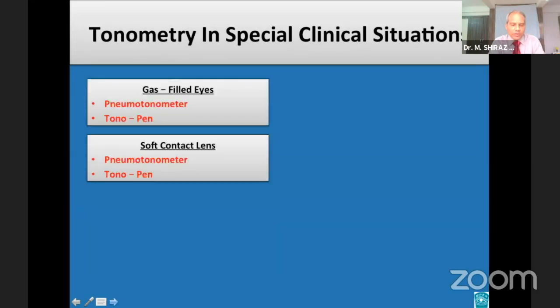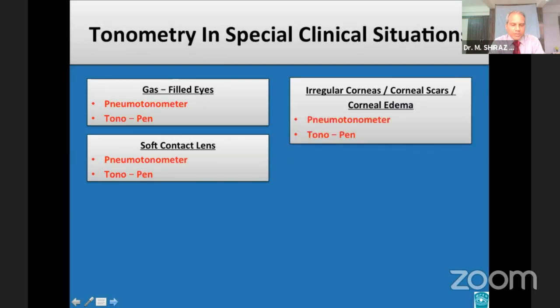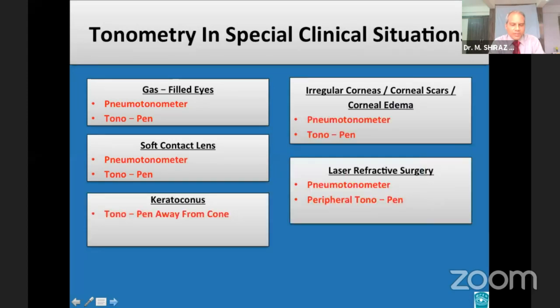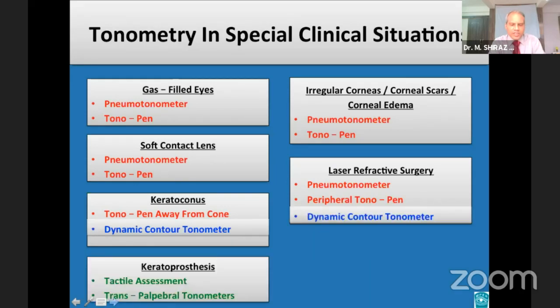No single tonometer is accurate or usable in all situations. In conditions like gas-filled eyes, over soft contact lenses, corneal pathologies, keratoconus, and post-laser refractive eyes, the pneumotonometer and the Tono-Pen are particularly useful. In addition, the DCT gives reliable measurements in keratoconus and post-laser refractive eyes. In eyes with corneal prosthesis, transpalpebral tonometers are useful devices, and when these are not available, one has to depend only on tactile assessment.